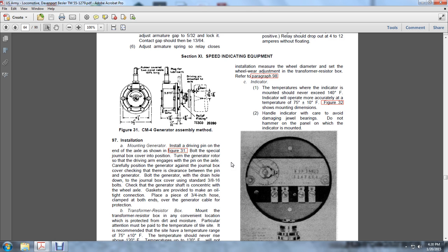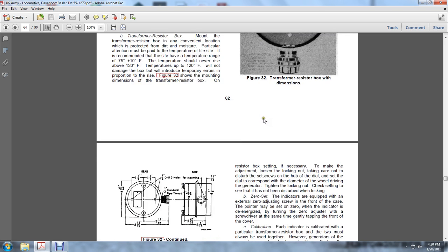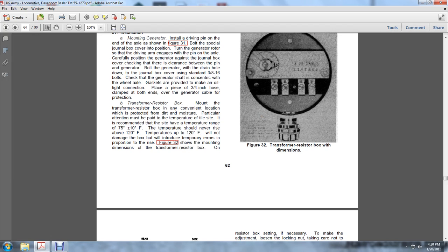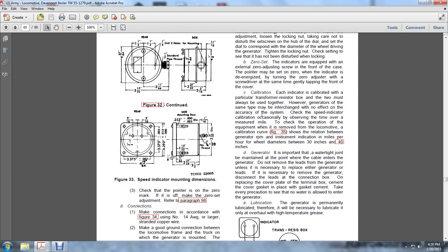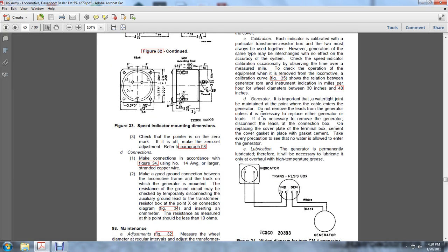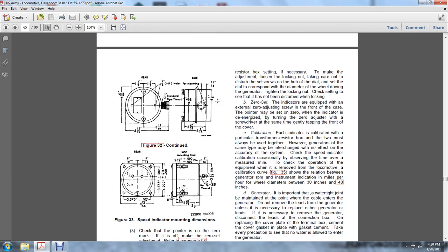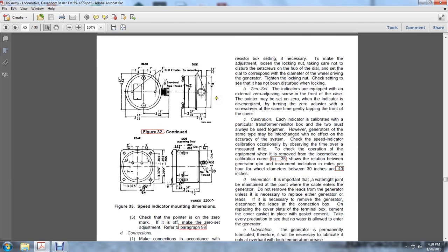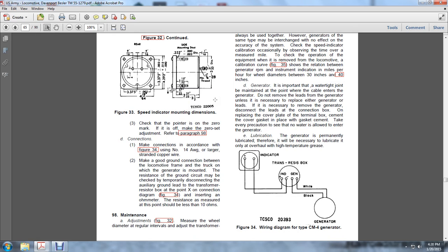Handle the indicator with care to avoid damaging the jewel bearings. Do not hammer on the panel on which the indicator is mounted. Figure 32 shows the transformer resistor box dimensions. Figure 33 shows the speed indicator mounting dimensions. Check the position of the zero mark, and if necessary use the zero set adjustment. Refer to paragraph 98. Connections: make the connections according to Figure 34.